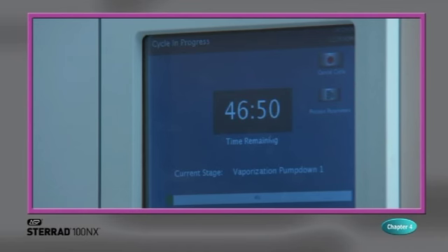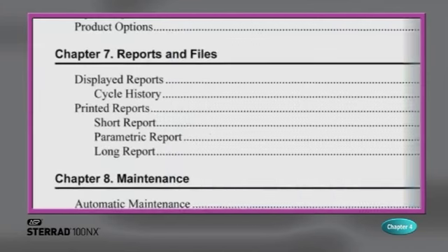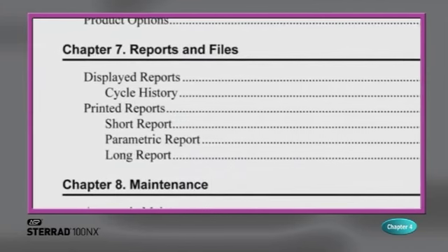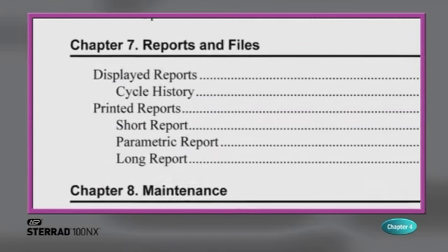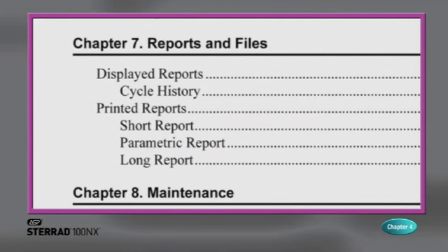The time remaining field updates as the sterilization cycle progresses. As each sterilization cycle stage runs, the screen displays the name of the stage. A moving bar graph also displays the percent of the cycle that is complete. For details about the current stage information, refer to the printouts in Chapter 7 of the User's Guide.